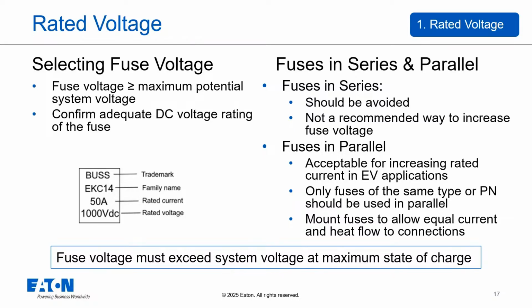However, using fuses in parallel is acceptable in EV applications for increasing the rated current capacity. It's not standard practice, but it can be used in EVs. If you do put fuses in parallel, only use fuses of the exact same type or part number. And importantly, mount them so that the current and heat distribution to the connections is equal across all parallel fuses. Remember, the fuse voltage rating needs to exceed the system voltage even at the battery's maximum state of charge.